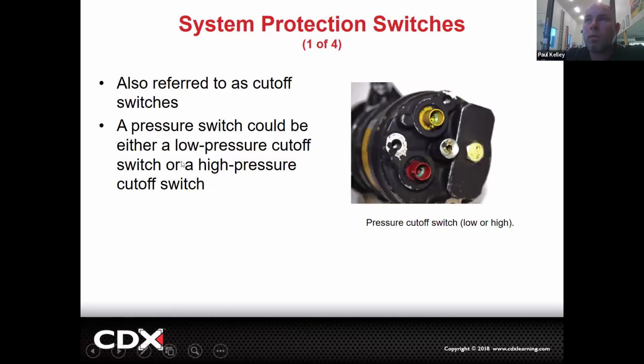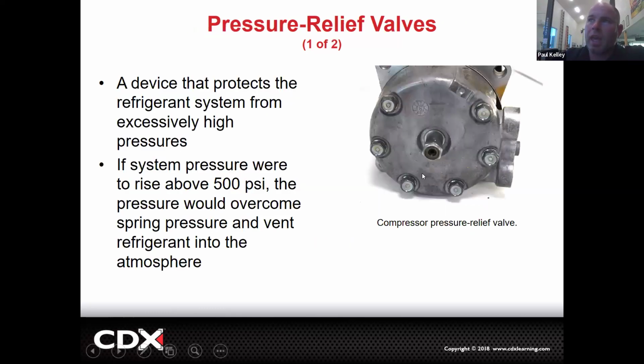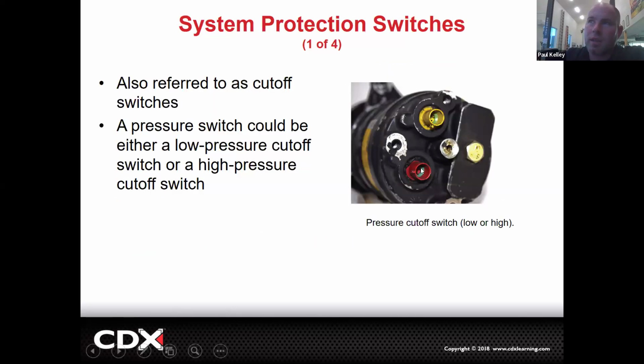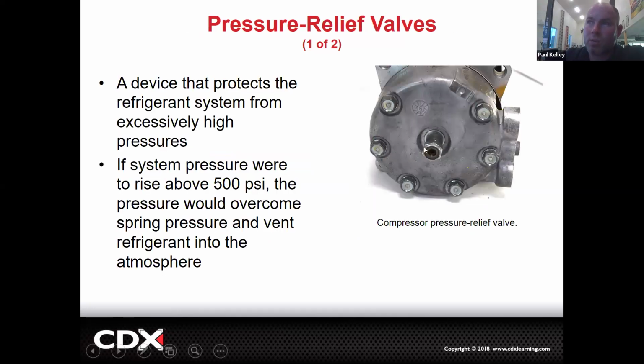All right. Or we can also have multiple different switches. So like we could have a low or a high cutoff switch. Let's go with this high cutoff switch. If your high pressure gets, let's say, above 400, this high pressure cutoff switch will open and it'll interrupt power to the compressor clutch. So the compressor will shut down and the pressure will come down. Typically, we don't have both a high pressure cutoff switch and a relief valve. A lot of times we'll have no compressor cutoff switch and just a relief valve. But if it has this, it should stop at 4 before it ever reaches 5.